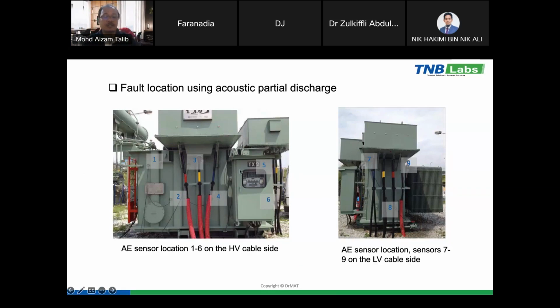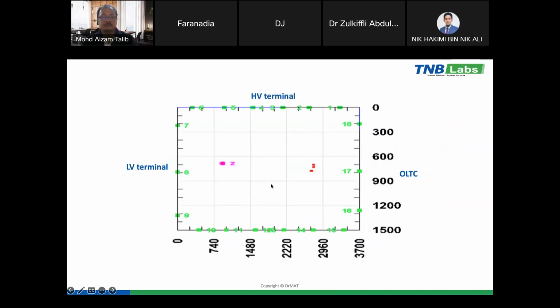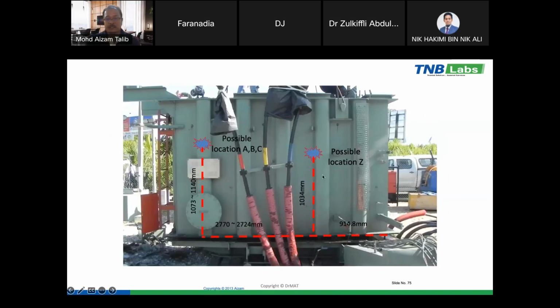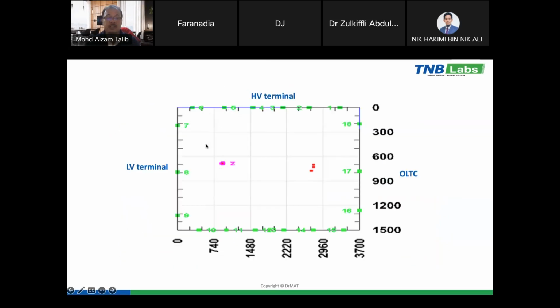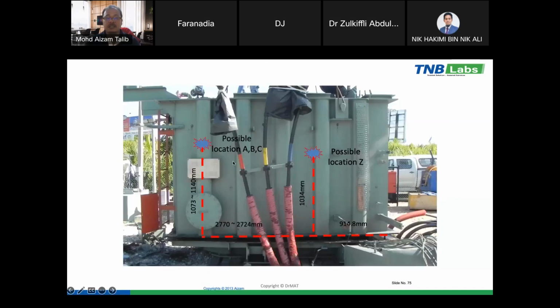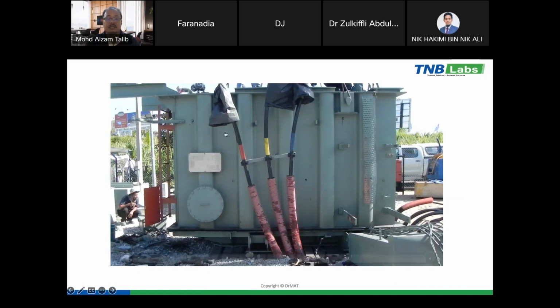So we put sensors around the transformer here, and then finally we located two possible areas. We measured again to find the location of the areas. This is the area of ABC here, and this is the possible area of Z. So we know that this transformer has a problem based on the dissolved gas analysis. There is overheating and partial discharge. Through this acoustic emission, the measurement also located a possible location of the high gas generation. So finally, we decided to untank the transformer. Here is the process of untanking the transformers.